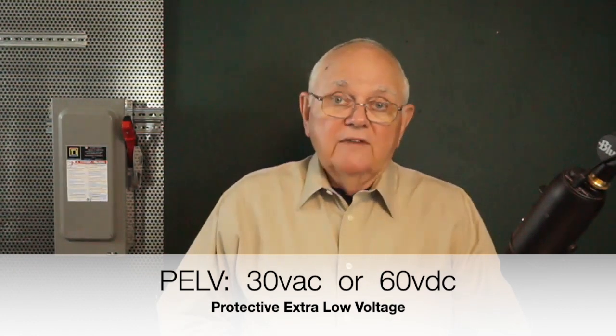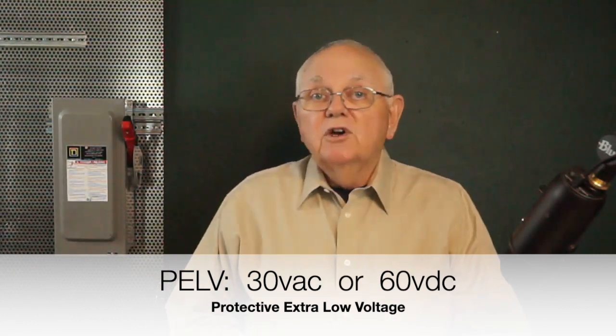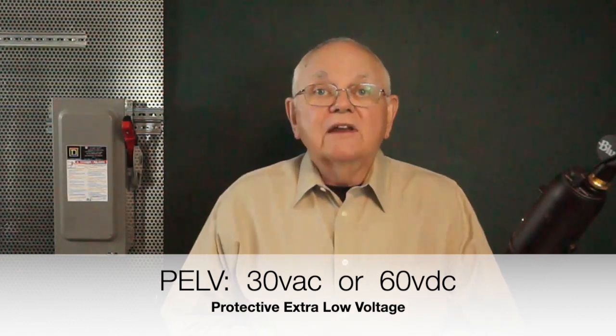Now, some of the other requirements for protection from electrical hazards, in addition to interlocks. Insulation, I can use insulation for protection. I can use double insulated components on the inside. Also something called protective extra low voltage. That's 30 volts AC or 60 volts DC. PELV, as it's commonly abbreviated, protective extra low voltage, we can use inside the machine to help protect from shock. Now, we should also remember what 70E tells us, that even though we're less than 50 volts, always look at the source of your power and see what the energy level is. You can be at less than 50 volts and still get a shock, or draw significant arc and so forth, simply because of the amount of energy that's available.